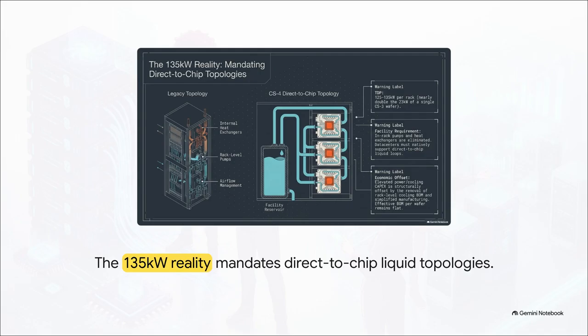But all this incredible density brings a stark facility reality check. While legacy topologies rely on standard airflow and rack-level pumps, the CS4 topology eliminates those entirely. With 3 overclocked wafers, a single rack now pulls a staggering 125 to 135 kilowatts of power, enough to run roughly 100 average homes, all in one rack. The mandate is clear: modern data centers must natively support direct-to-chip liquid cooling loops. Legacy airflow just cannot handle this thermal density.